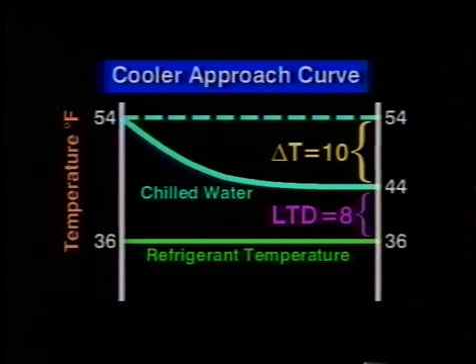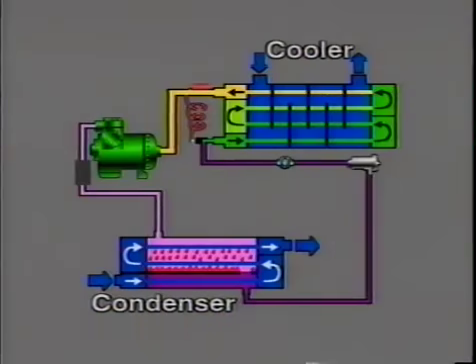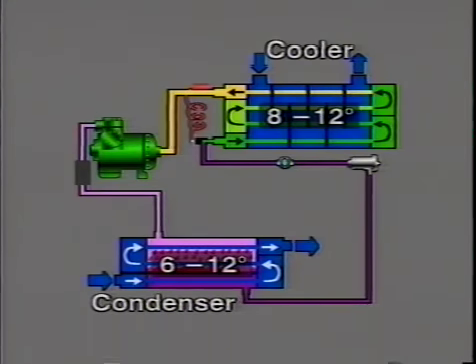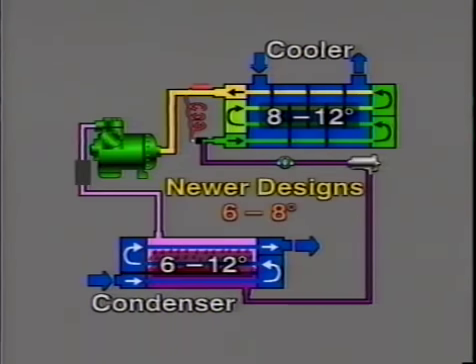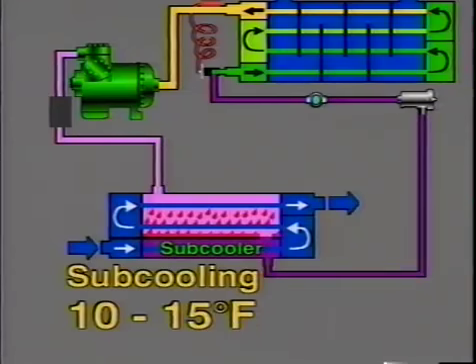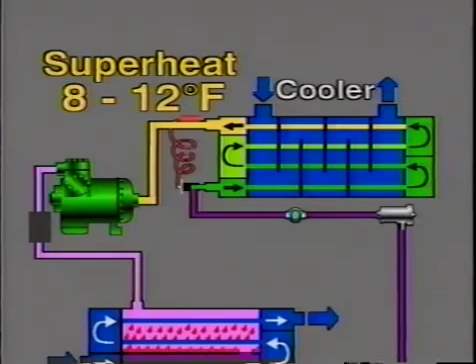LTD is the difference between the leaving water temperature and the saturated refrigerant temperature in the cooler or condenser. A typical LTD is 8 to 12 degrees Fahrenheit for a cooler and 6 to 12 degrees Fahrenheit for a condenser. Newer chillers with high heat transfer efficiencies have cooler and condenser LTDs in the 6 to 8 degree Fahrenheit range. Reciprocating compressor chillers typically have 10 to 15 degree Fahrenheit subcooling leaving the condenser and 8 to 12 degrees superheat leaving the cooler.